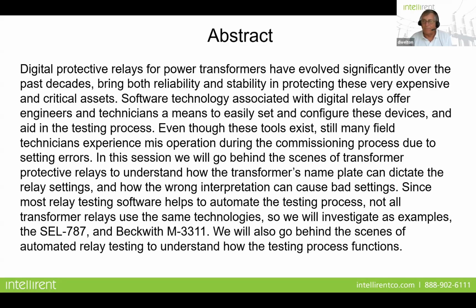Over the past decades, both reliability and the stability of these critical assets has improved with digital technology. I mean, in most all cases, in any new application, we have moved on from the old electromechanical days to digital relays. And with digital relays, we don't worry about things like calibration. We don't worry about contacts going bad, or the things that we were concerned about with electromechanical relays.